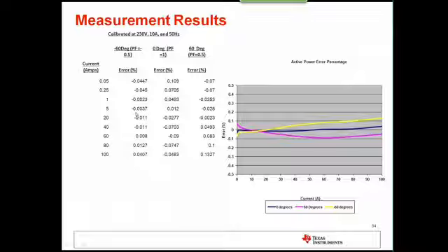Whenever your voltage and your current are in phase, this is the error that we can expect from 0.05 to 100 amps. We test this in our lab with a reference meter. Regrettably, we can't do that here, we don't have the accuracy with the tools available, but back in the smart grid lab we can verify all of this data.